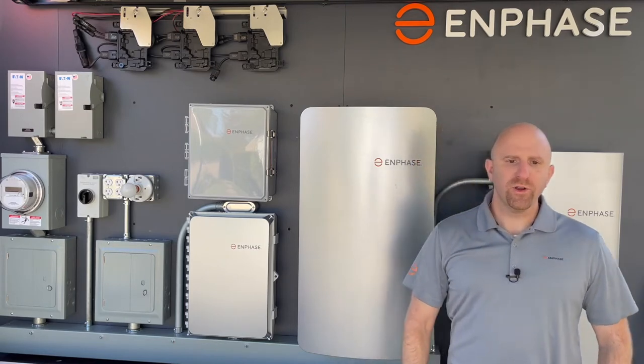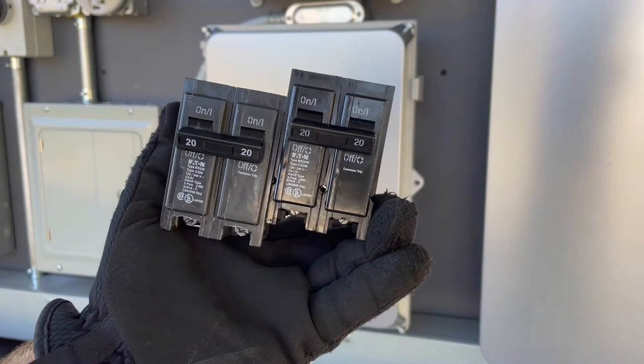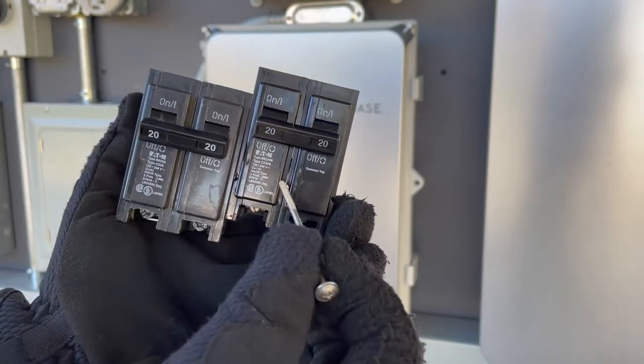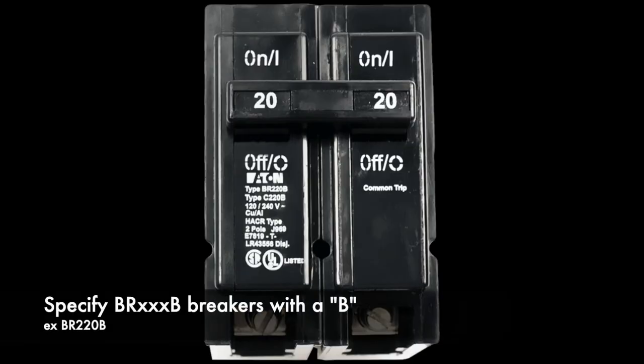They cannot create grid voltage without an IQ System Controller. With Eaton breakers that are 50 amps or less, you will need to specify models that end in the letter B for bolt-down compatibility, as they feature a hole that allows for a bolt to pass through. An example is a BR-220B — this is a two-pole, 20-amp breaker that's bolt-down kit compatible.